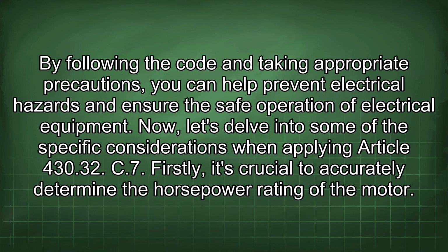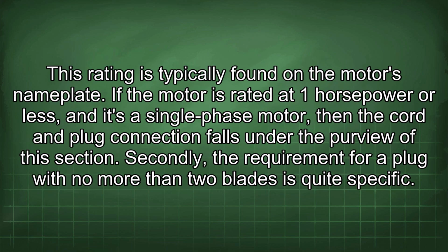Now, let's delve into some of the specific considerations when applying Article 430.32 C. Firstly, it's crucial to accurately determine the horsepower rating of the motor. This rating is typically found on the motor's nameplate. If the motor is rated at 1 horsepower or less, and it's a single-phase motor, then the cord and plug connection falls under the purview of this section.